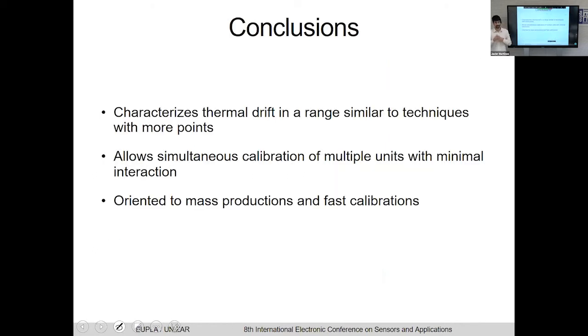In general, we think that the proposed model characterizes the thermal drift in a range very similar to techniques that require a lot more points and therefore a lot more time. And our technique allows for simultaneous calibration of units and in-field calibration or recalibration. We think that this technique is most interesting for factory environments where mass production requiring individual calibration can make the cost of the products go high really fast. Thank you for your attention.